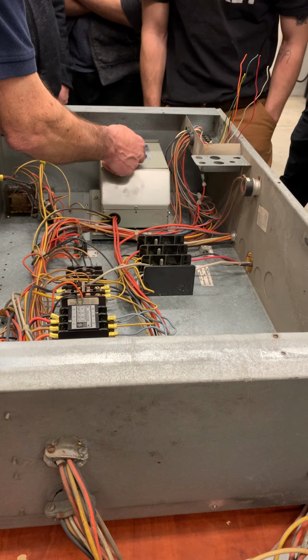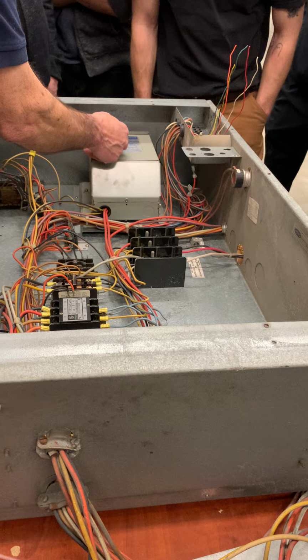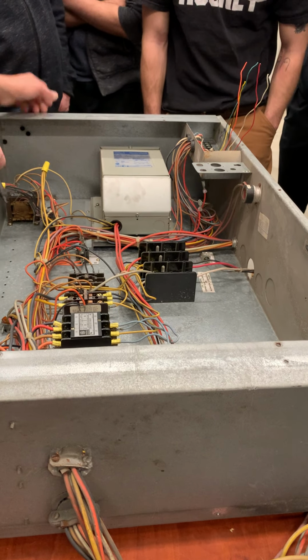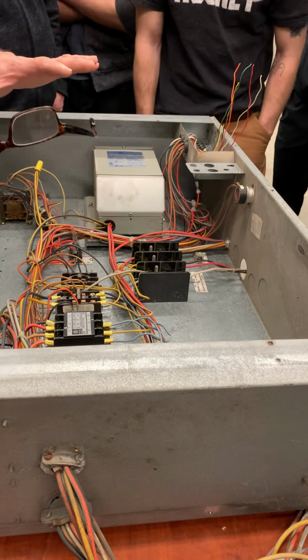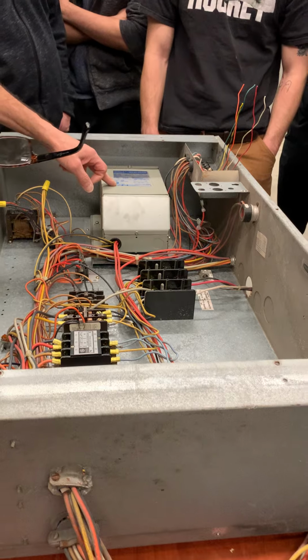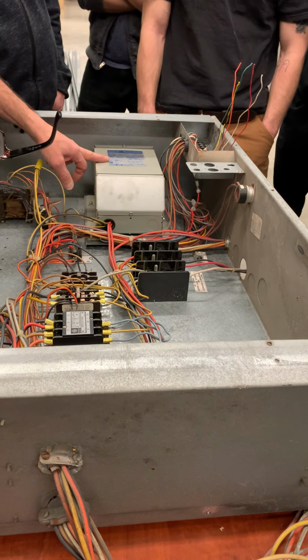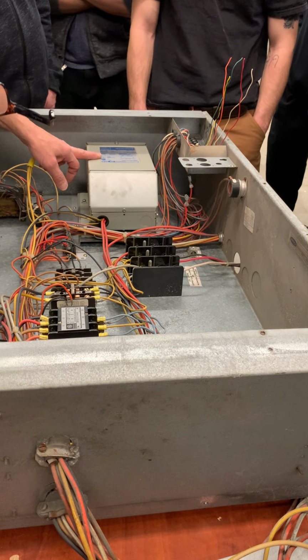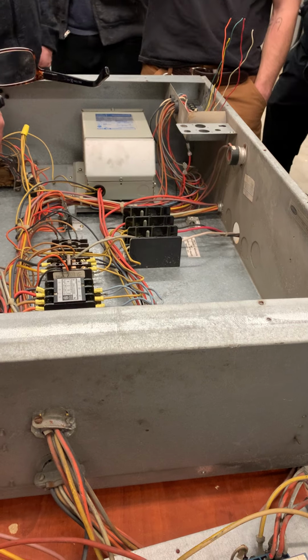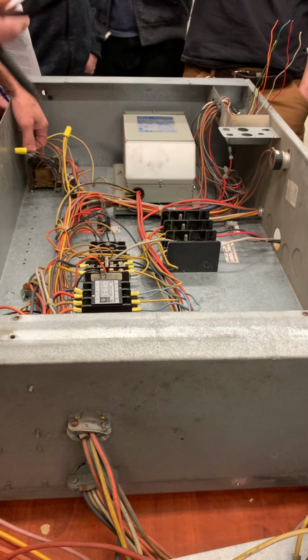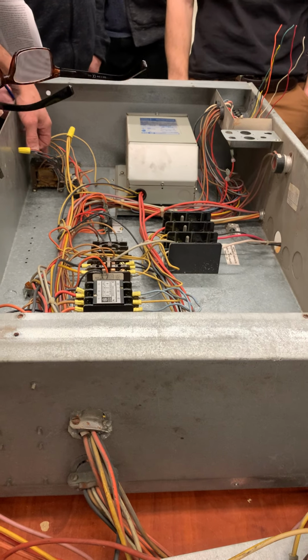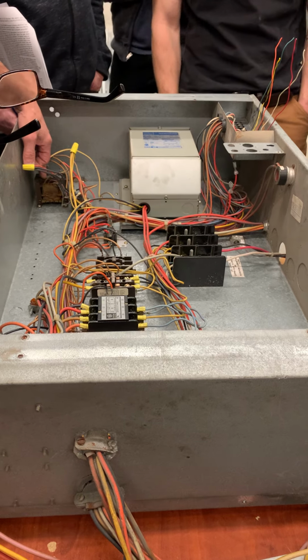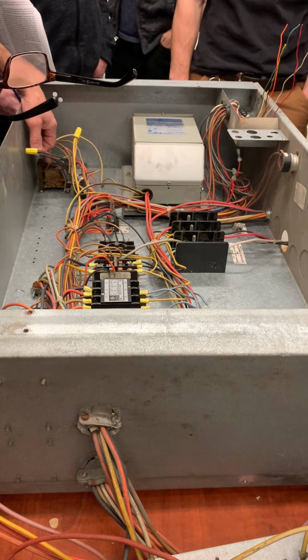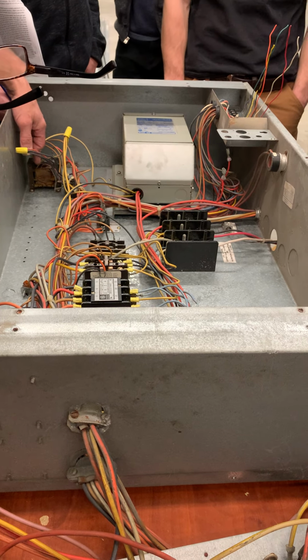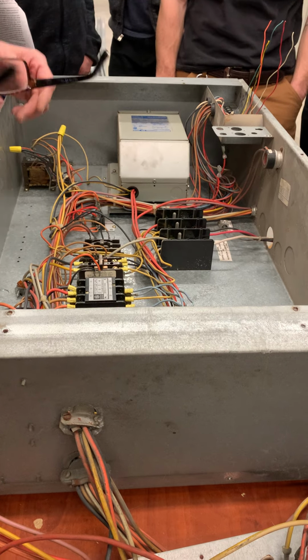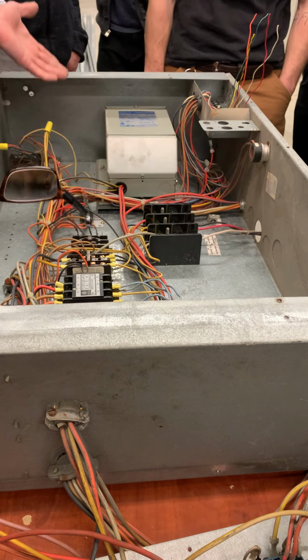Over here, I got some extra wires. So on the secondary side, depending how I hook it up, I can get 120 or 240. So what they're doing here is taking the 600 volts in, and they're going to come out with 120 or 240. And what are they going to use that for? The inducer motors. Okay, on commercial they're going to be 240. They power this transformer over here. I need input voltage for this item, and I don't want to put 600 in here. So I'm going to put in the 240 over to this one. So 240 comes into here, 240 goes to the inducer motors. Fair enough? Is there anything in here we haven't covered?